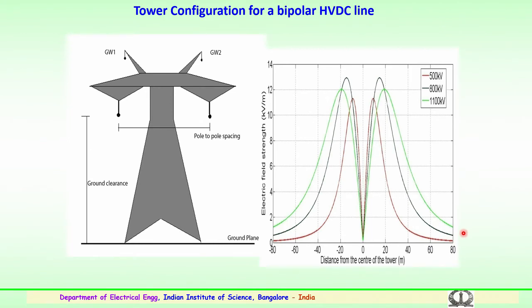This is a similar study conducted for the tower configuration for bipolar HVDC transmission lines for various voltage levels, 500 kV, 800 and 1100 kV lines. The data for the tower details have been obtained from the utility and also from the literature. This is again a schematic of the HVDC transmission tower. You can see the ground clearances where the conductors are connected. This is a bipolar two-pole DC line. GW1 and GW2 are the ground wire connections 1 and 2 for a tower. This is the ground plane, and the distance between the two conductors gives the pole to pole spacing, which as per the standards for 500, 800 and 1100 kV has been taken into consideration while estimating the electric fields.